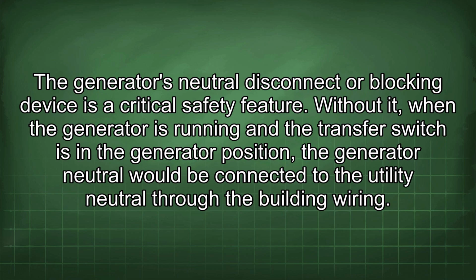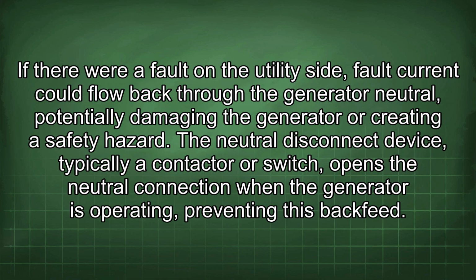The generator's neutral disconnect or blocking device is a critical safety feature. Without it, when the generator is running and the transfer switch is in the generator position, the generator neutral would be connected to the utility neutral through the building wiring. If there were a fault on the utility side, fault current could flow back through the generator neutral, potentially damaging the generator or creating a safety hazard. The neutral disconnect device, typically a contactor or switch, opens the neutral connection when the generator is operating, preventing this backfeed.